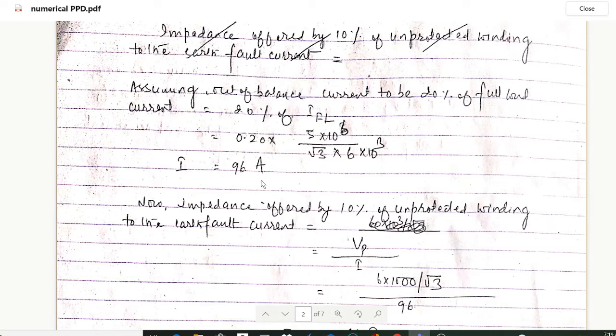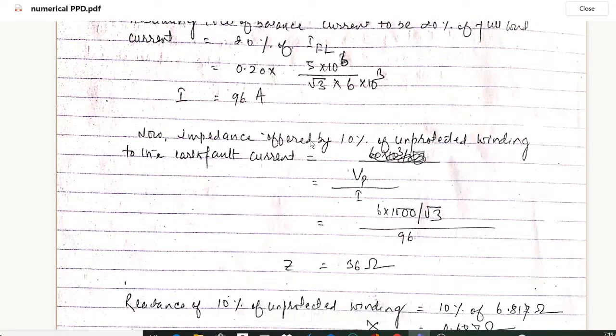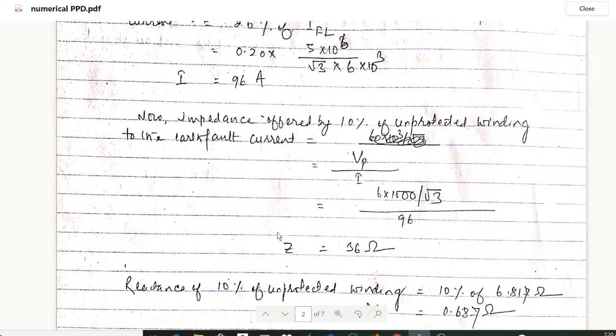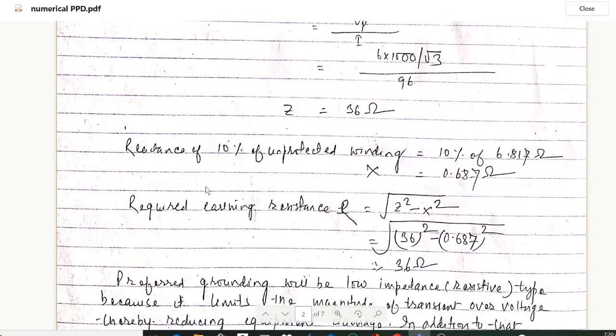Now impedance offered by 10 percentage of unprotected winding to the earth fault current: it will be Vp upon I. We have obtained kV as 6 kV, and here we have to use phase voltage. So 6 kV means 6 into 1000 upon root 3, and I means 96 amperes. We will get the value of Z, so Z will be 36 ohms.